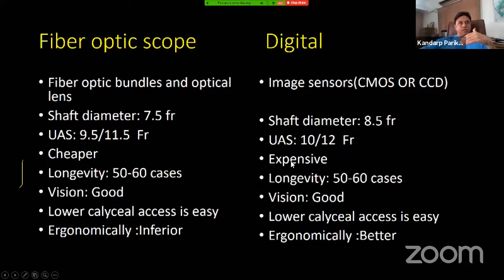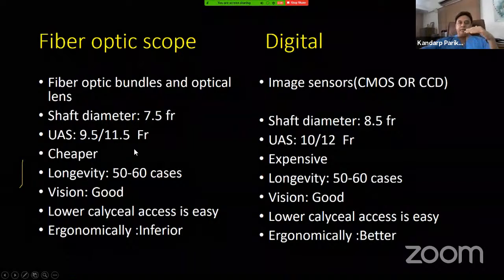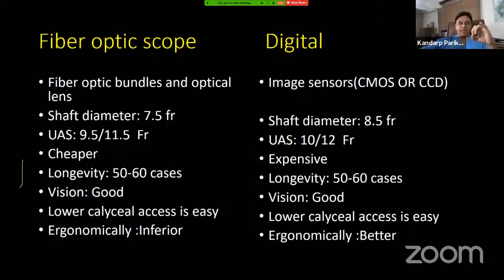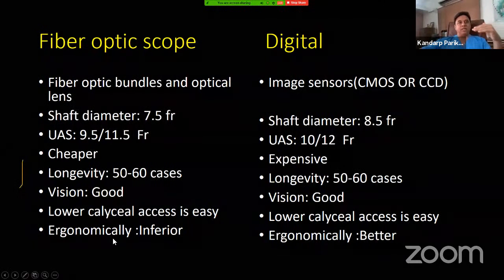Digital scopes are expensive. Secondly, the diameter of the flexible scope is 7.5 French, while the smallest digital scope is 8.5 French. So it's slightly bigger in diameter. That's why it will require a 9.5 by 11.5 French ureteral access sheath for a flexible scope, while for a digital scope, you need a little larger ureteral access sheath, so 10 by 12. The diameter of the Indian ureter is very, very small. That's why sometimes you find it very difficult to put in a 10 French ureteral access sheath. That's why you need to have a fiber optic scope.